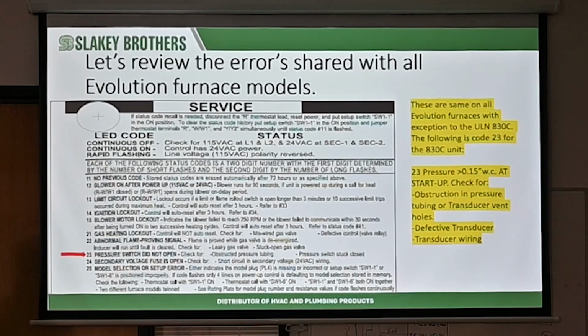Basically, blower on after power up. So that means you got to call for heat, and you open up the door, you're checking out what's going on, you close the door, and all of a sudden it starts flashing. And it's a 12. Well, that's because the thermostat was already asking for heat. So as soon as that unit came on with power, R to W was closed, or R to W1, W2, whatever, they were closed. And it's just going to turn on the blower motor and cool down the heat exchanger, just in case there was a power outage.